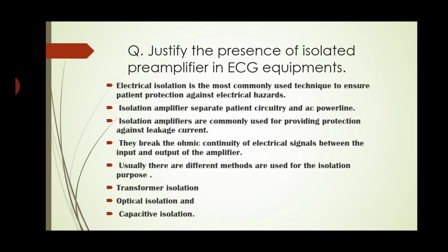Isolation amplifiers separate patient circuitry and the AC power line. They are commonly used for providing protection against leakage current. They break the ohmic continuity of electrical signals between the input and output of the amplifier.